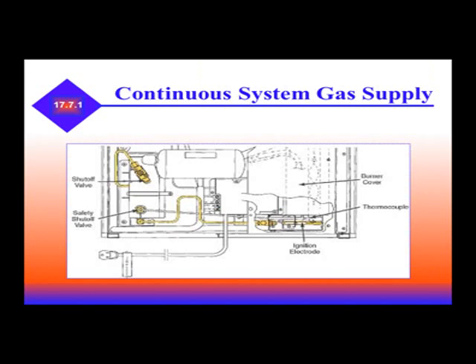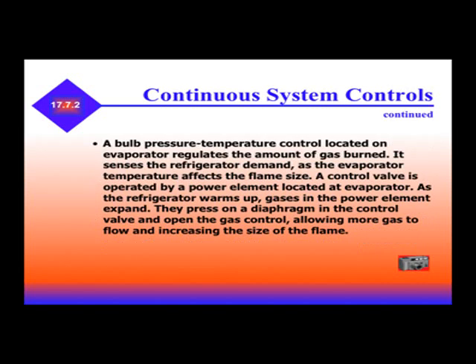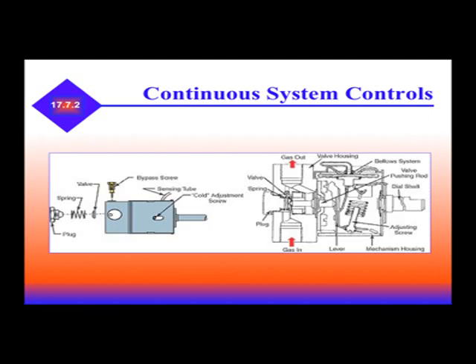At the bottom of an absorption refrigerator, you have shutoff valves, ignition electrodes, thermocouples, and covers. Heat and gas valves automatically control the amount of gas burned, and the flame size varies on demand. Electronic ignition ignites the flame, and the system may have an automatic flame relight system. All continuous systems require gas volume and safety controls. A bulb pressure-temperature control located on the evaporator regulates the amount of gas burned. It senses the refrigerator's demand as the evaporator temperature affects the flame size. As the refrigerator warms up, gases in the power element expand, pressing on the diaphragm in the control valve, opening the gas control and allowing more gas to flow, increasing the flame size.